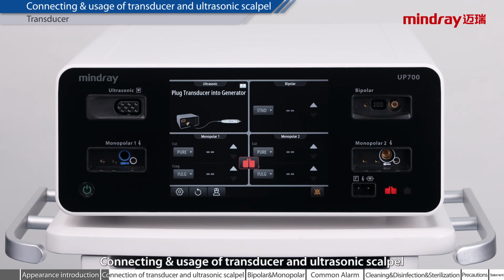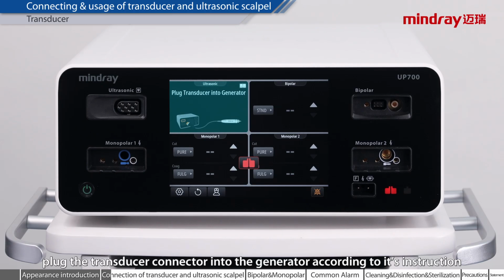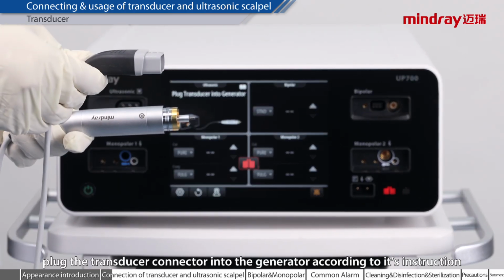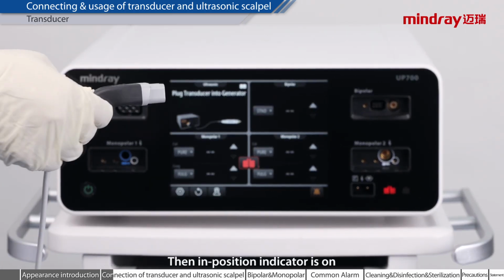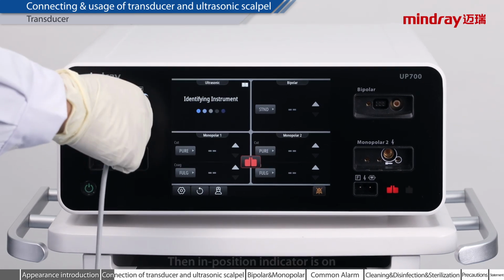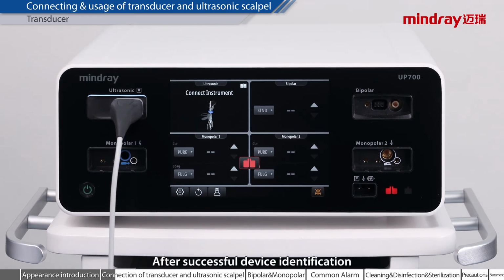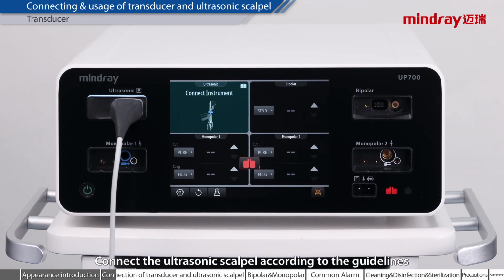Connecting and usage of the transducer and ultrasonic scalpel. Firstly, plug the transducer connector into the generator according to its instruction. Then, the in-position indicator is on. After successful device identification, connect the ultrasonic scalpel according to the guidelines.